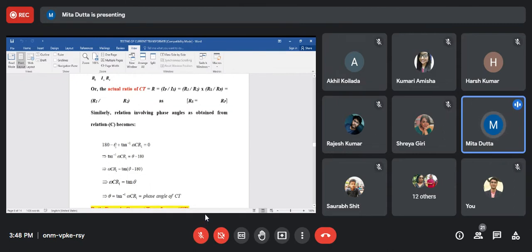So from here, ultimately we get theta equals tan inverse omega C R1, and this is the phase angle of the CT — meaning not an ideal CT but the actual CT. This is treated as an error because ideally the angle would be 180 degree, but instead of 180 degree we get angle theta, so it is treated as a phase angle error. Clear? The phase angle error again depends upon C and R1.